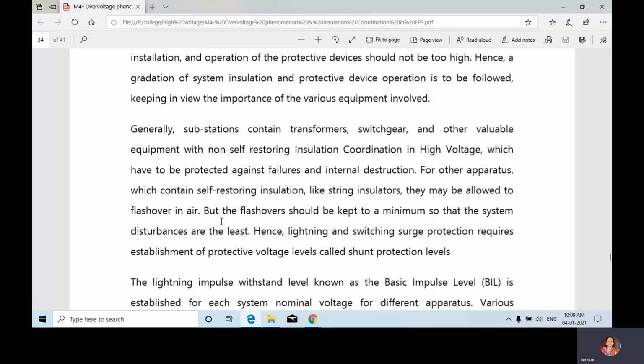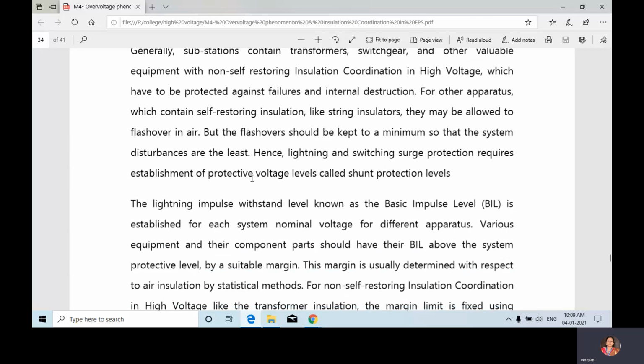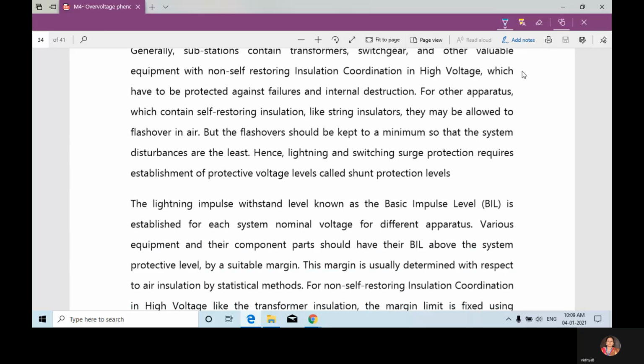It will allow the flashover in air, but the flashover should be kept to a minimum so that the system disturbances are the least. Lightning and switching surge protection requires establishment of protective voltage levels called shunt protection levels.